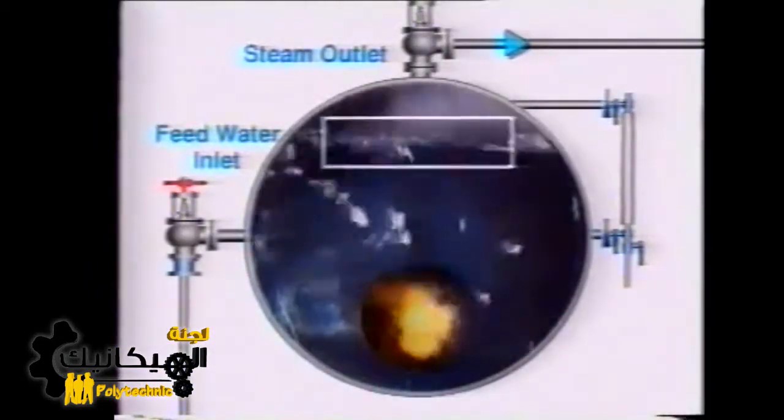The water levels in a boiler need to be kept within a very narrow operating band. Too high leads to carryover. Too low, and the low water level alarm will shut down the boiler. And, as we have seen, many factors can affect this delicate balance. Even at moderate steady loads, feed pump on-off operation causes the boiling rate to be suppressed, followed by a swell which takes the level above the pump-off level. An increase in demand also produces sudden level fluctuations. Furthermore, these effects will compound to produce even larger fluctuations if the circumstances occur together.